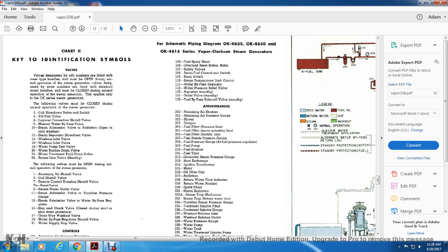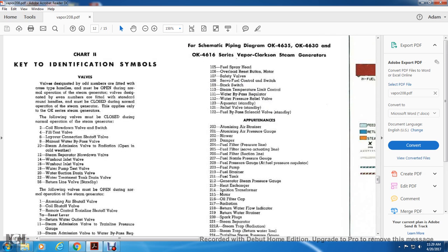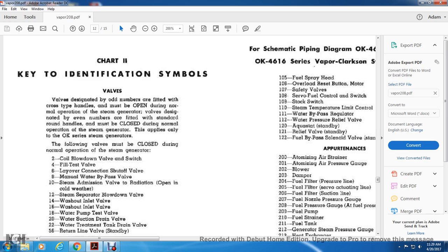Alright, chart 2. Valves designated with odd numbers are fitted with the cross-type handles and must be opened during normal operation. Steam generator valves designated with an even number are fitted with round handles and must be closed during normal operation. So round is closed, cross is open on operation. This applies to the OK series numbers. The closed round ones are even.